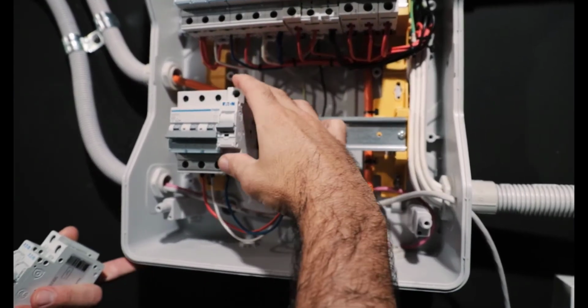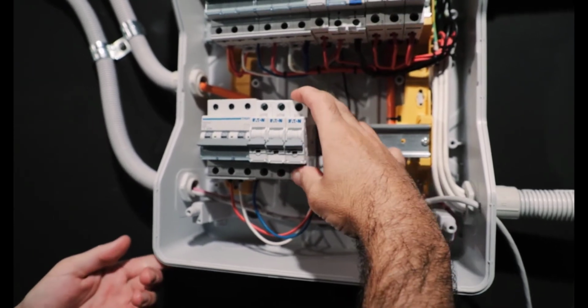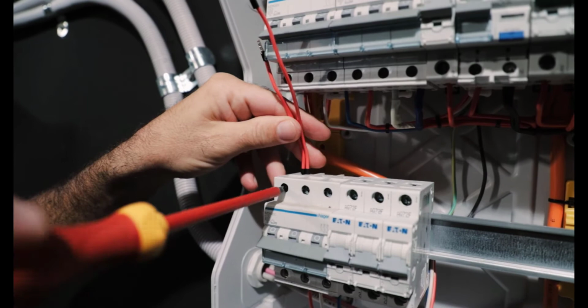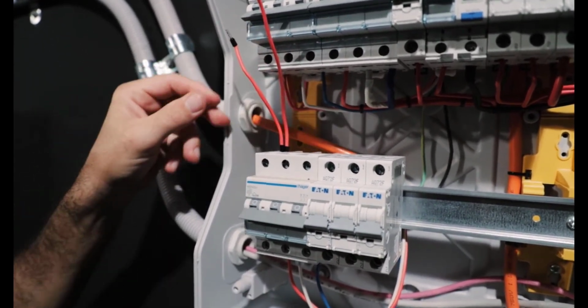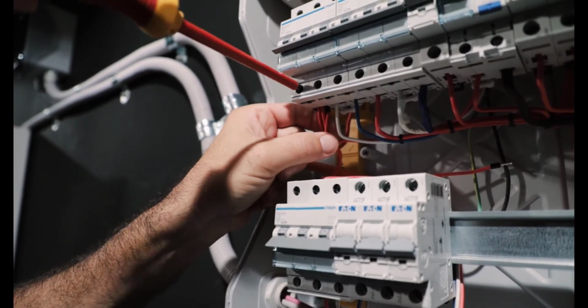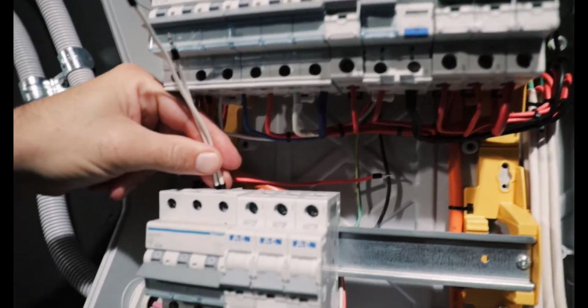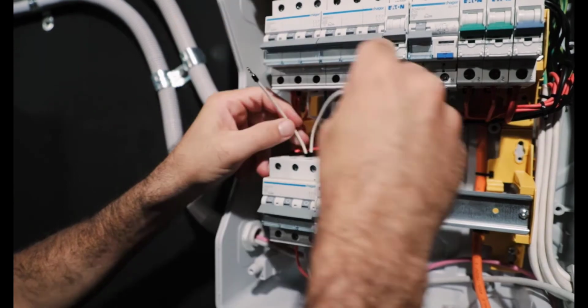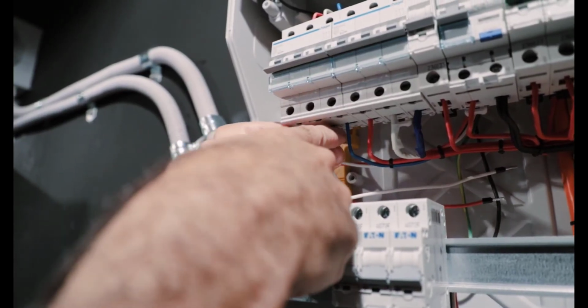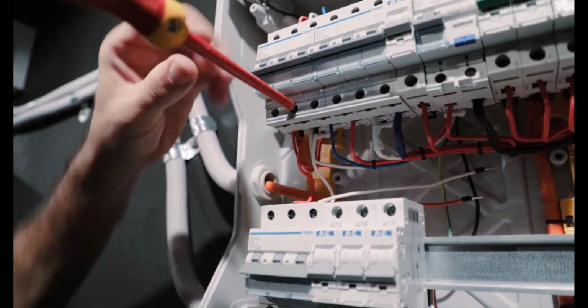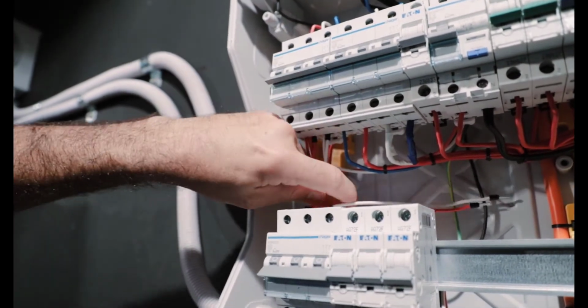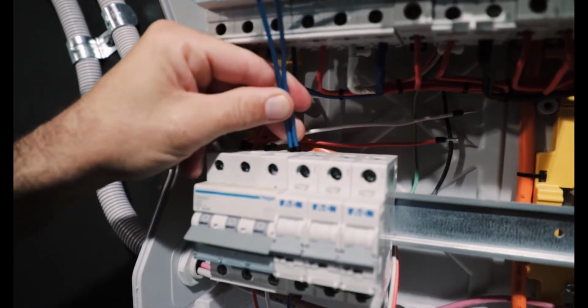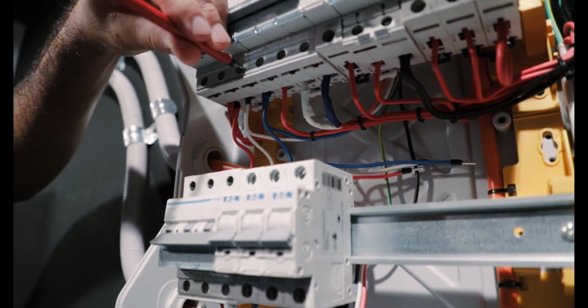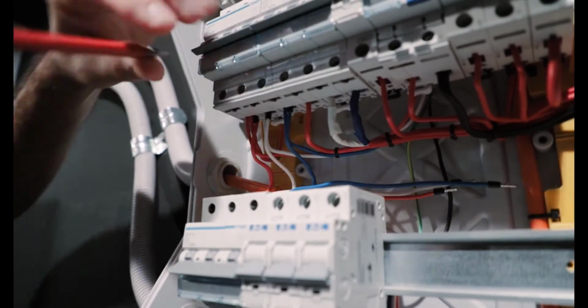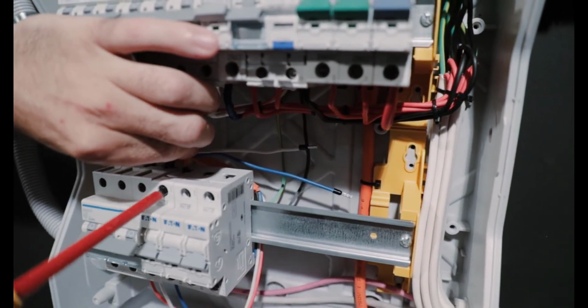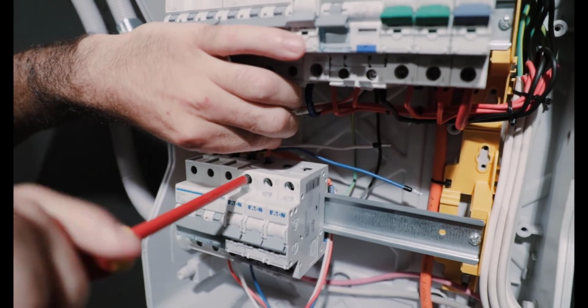If, however, you have got a property with a whole series of different subboards, you may have more than one bank of boards coming off separate other boards. The PV may not necessarily even go into the main switchboard, it may go into a different subboard. What this means is that if you can bring the sonnen system back to the main subboard or the main board, all you need to do is measure the grid connection, and it doesn't matter where everything else is integrated, even where the solar is integrated, as long as you can get your CT onto that solar supply, it'll measure, and the measurement of the sonnen system will then work out what the loads are. So all it actually needs to look at is the grid. So it really is giving the installer options depending on how a property has been wired and what they're going to find when they rock up on site. It gives them the best of both worlds option on how to wire or position the CTs. It's not a fixed requirement. You can either go grid measurement or consumption measurement.